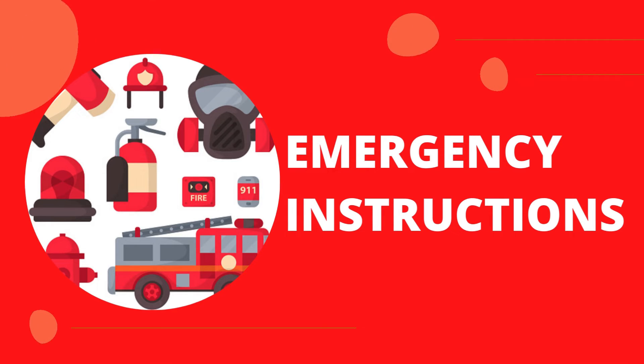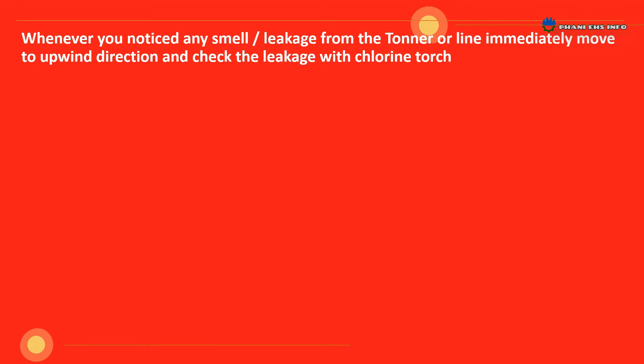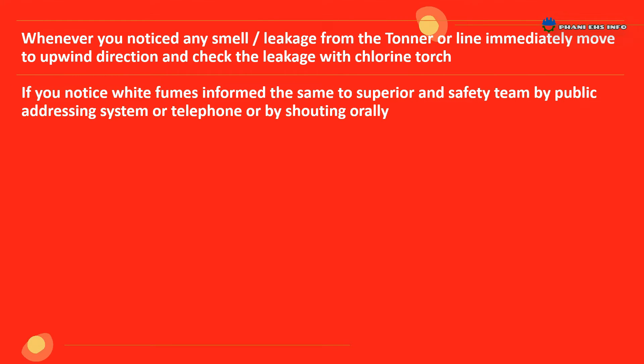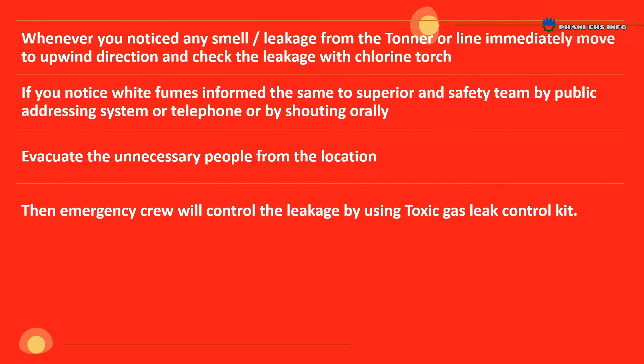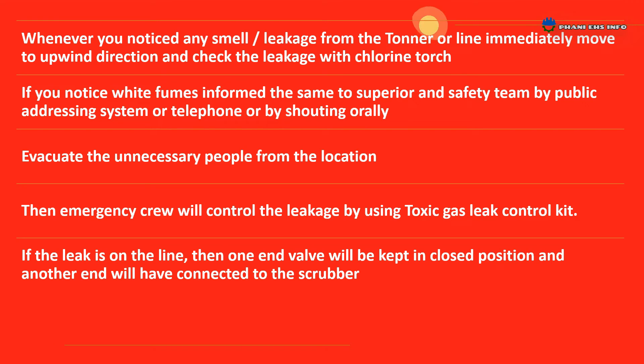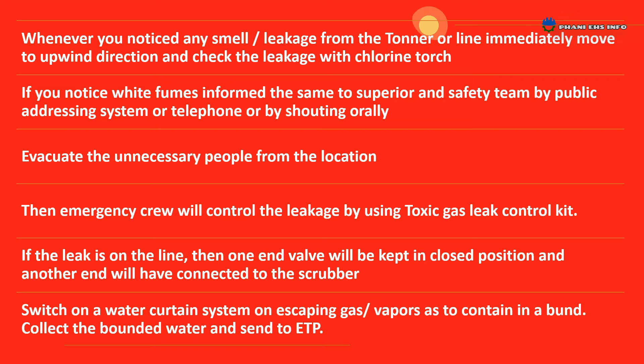Emergency Procedure in Case of Ammonia Gas Leak: Whenever you notice any smell or leakage from the tonner or line, immediately move to the upwind direction and check the leakage with a chlorine torch. If you notice white fumes, inform the same to superior and safety team by public addressing system, telephone, or by shouting orally. Evacuate unnecessary people from the location. If the leak is on the line, one end valve will be kept in closed position and the other end connected to the scrubber. Switch on the water curtain system on escaping gas vapors to contain within a bund. Collect the bounded water and send to ETP.